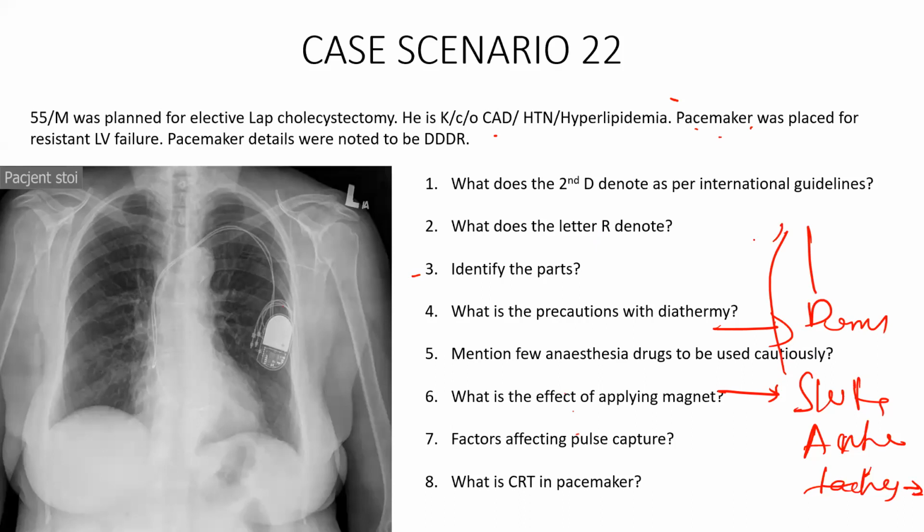When there is an emergency surgery where you don't have time to reprogram the pulse generator, you can apply a magnet so that the magnet takes the pulse generator to a fixed mode. Do you understand this point? The rest, all unmute and tell me.